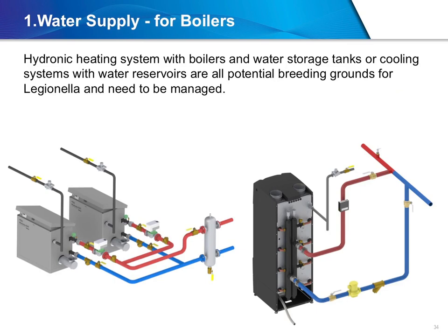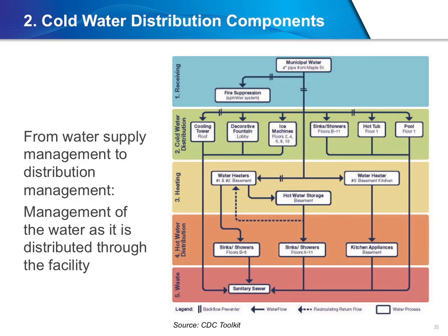Some of the water used in buildings is not for direct contact with people, but is used instead for heating and cooling systems. Hydronic heating systems with boilers, for example, use water storage tanks to balance out the water requirements of the system. That water could be a breeding source of bacteria if the temperature conditions and other circumstances such as scale are favorable. Once the water is in the facility, it needs to be distributed appropriately for use on demand. Depending on the size and nature of the facility, that may prove to be rather complex, which is why the schematic flow diagram of a water system is important as part of a water management program.